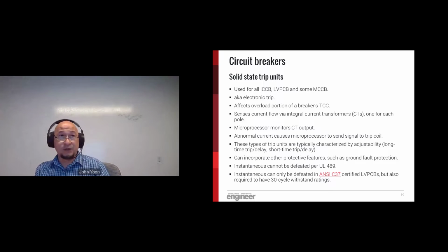Now, with a fixed mechanism like that for a generic fuse or circuit breaker, we have pretty well-defined characteristics regarding how each device will respond to magnitudes of overcurrent. But in an electrical distribution system, we have multiple devices in series, each with its own characteristic time current curve. When we design electrical distribution systems, we're trying to isolate an abnormal condition to the smallest portion of the distribution system. We want the device closest to the fault or overload to operate first, to have what we call selective coordination. With multiple devices in series, there's bound to be some overlap and that will lend some uncertainty regarding what device will trip first.